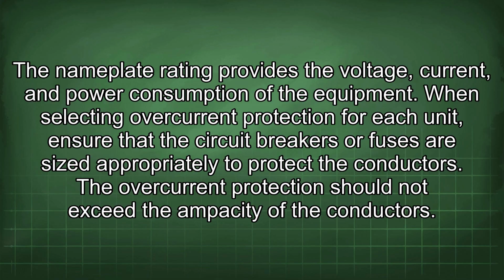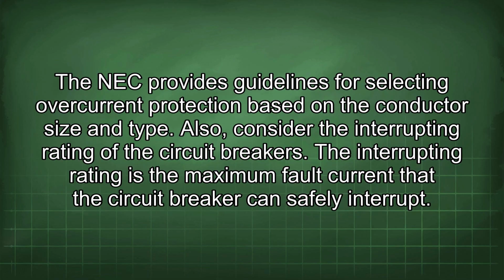When selecting overcurrent protection for each unit, ensure that the circuit breakers or fuses are sized appropriately to protect the conductors. The overcurrent protection should not exceed the ampacity of the conductors. The NEC provides guidelines for selecting overcurrent protection based on the conductor size and type.